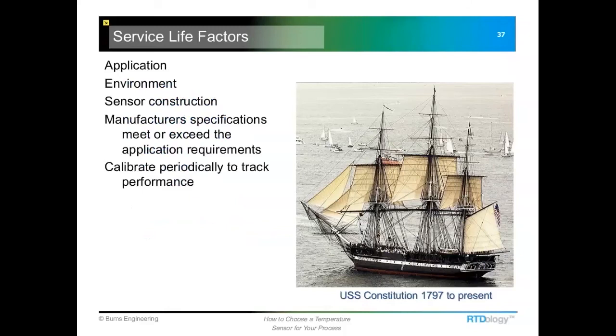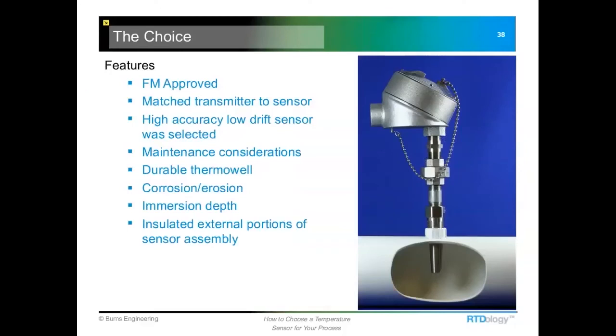The same thing holds true for temperature sensors. It's not typically just install it and forget about it. You do need to go back and calibrate it every once in a while, make sure that it's still doing what it's supposed to be doing. And looking at all the protection on the instrument side and also on the process side helps lengthen the service life of that component.